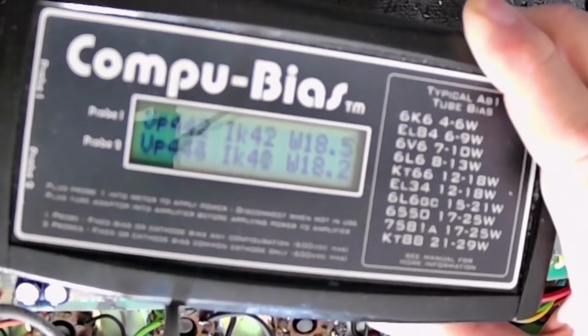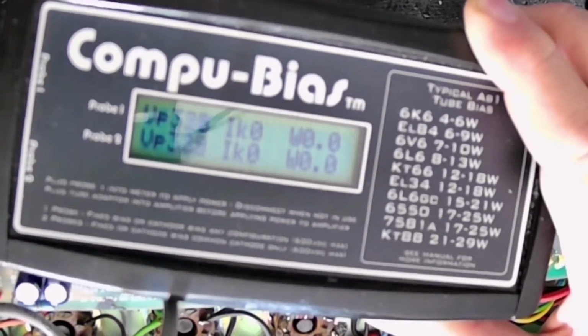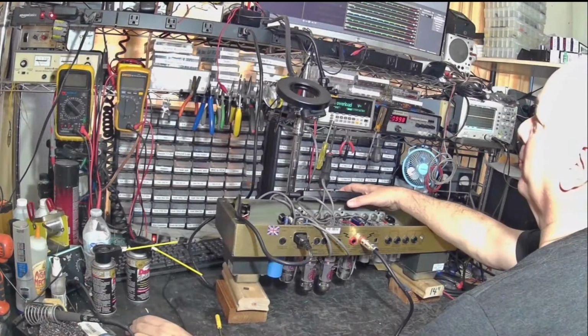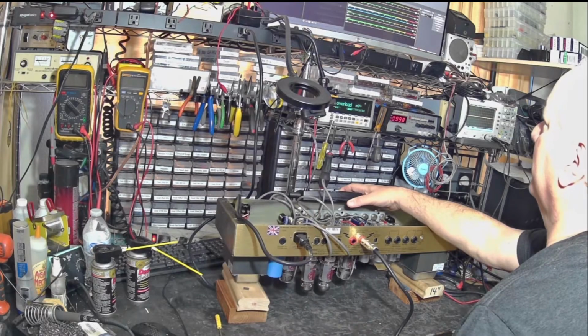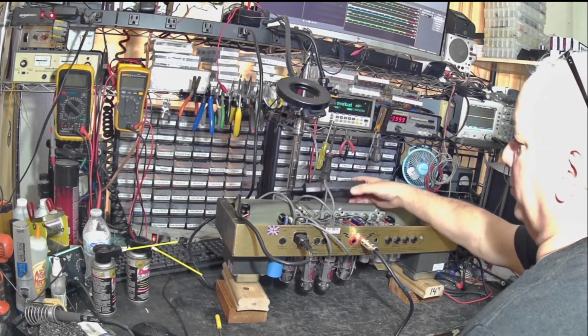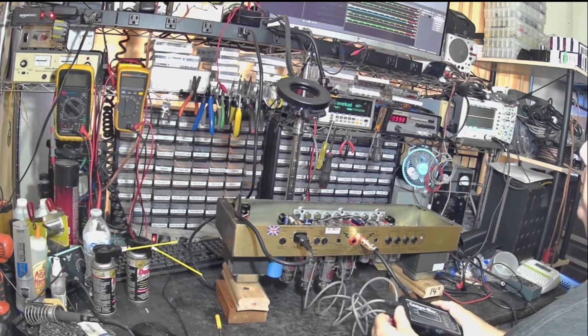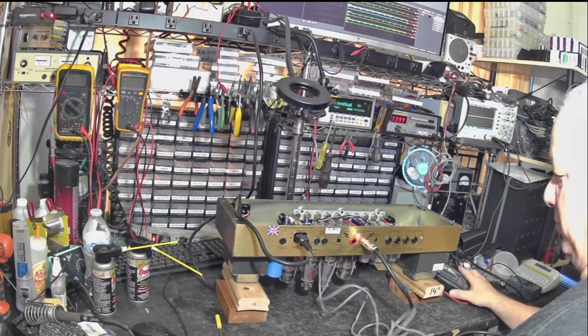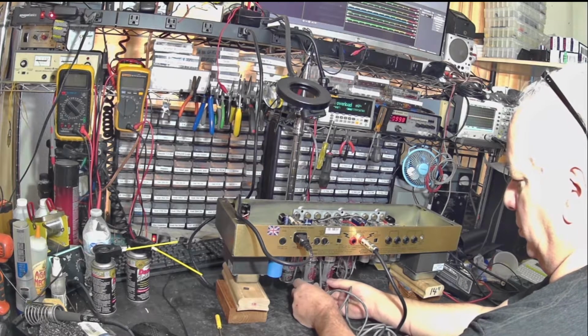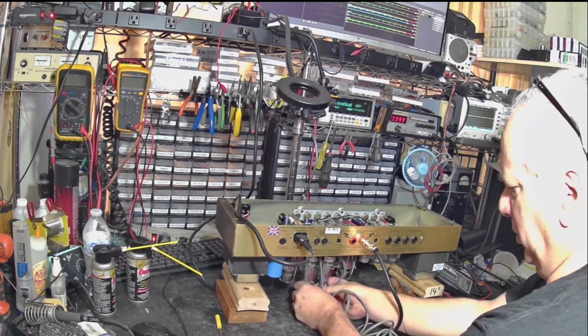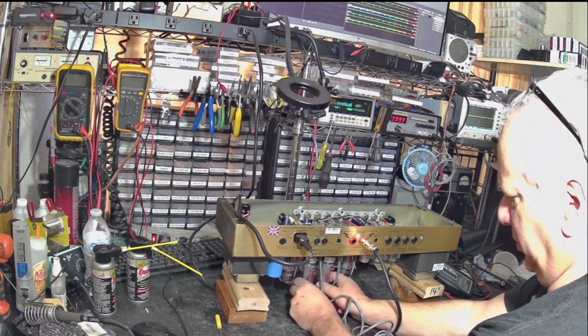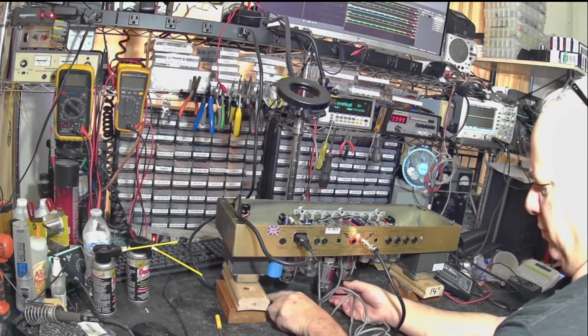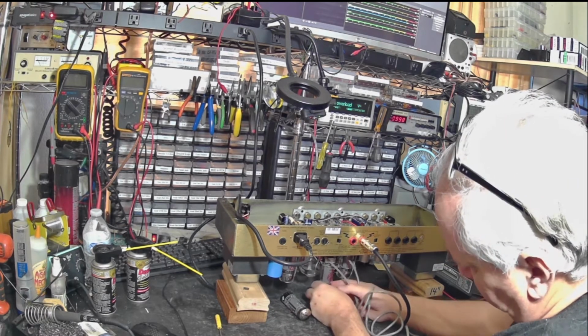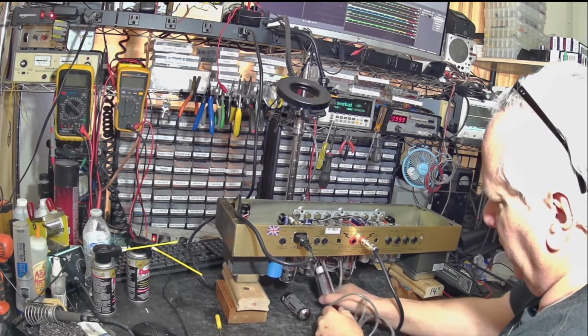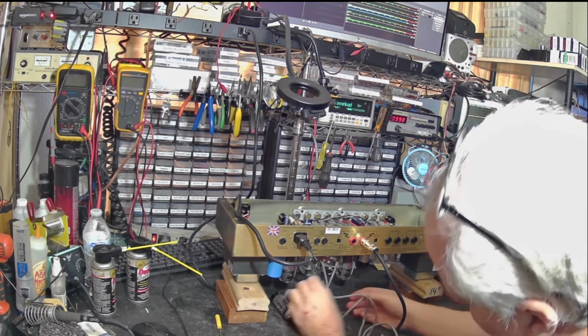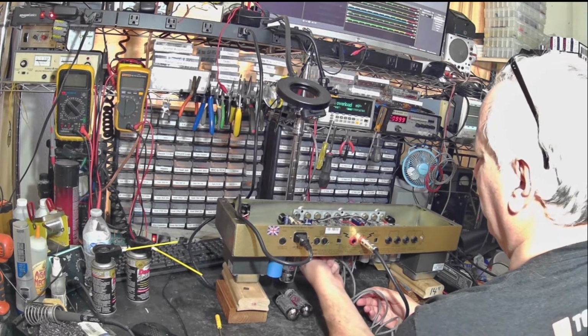I'm going to go ahead and power down. There goes the standby. There goes the power switch. And I'm going to unhook the bias tool, put it away. We don't need any more. Shut off when I pull these little cables out. I'm going to remove the tubes. Be careful when you touch tubes. Sometimes they're hot. We didn't have it on for a very long time, so they're tolerable. A lot of times I'll reach for a glove. They're a little bit on the toasty side. If you have a glove, keep your fingers from getting burnt by the tubes when they're very hot.